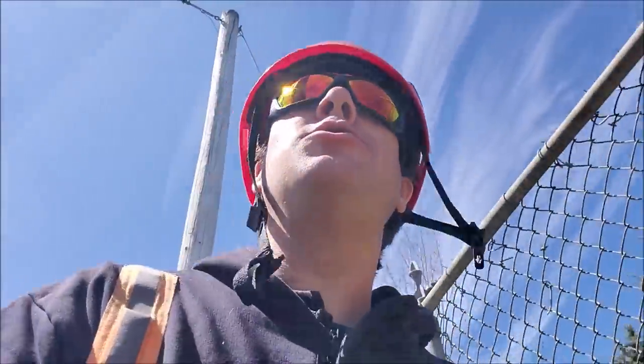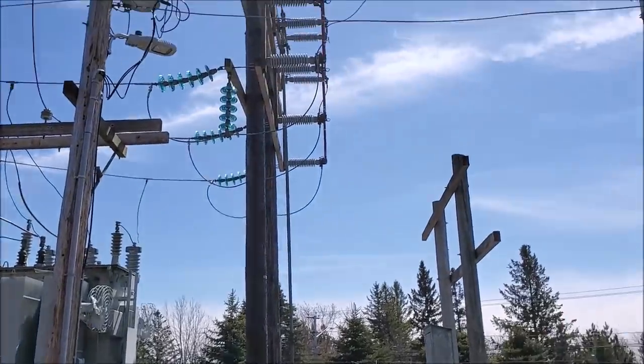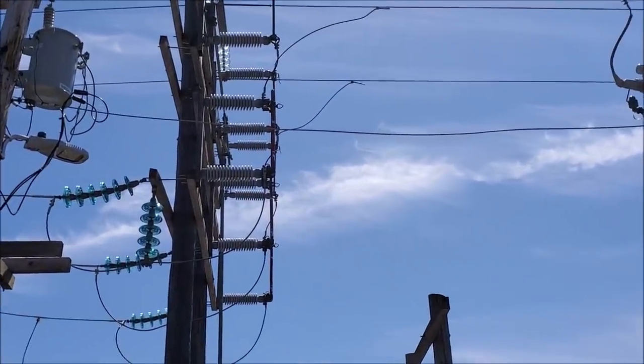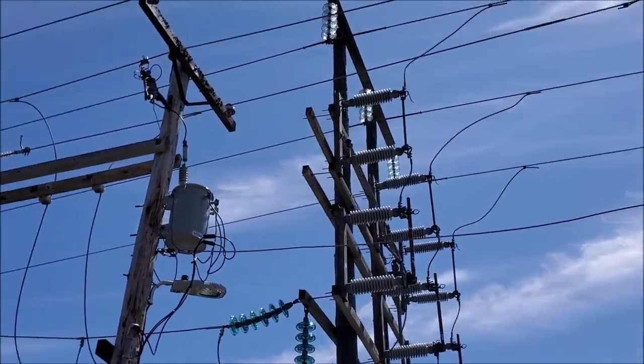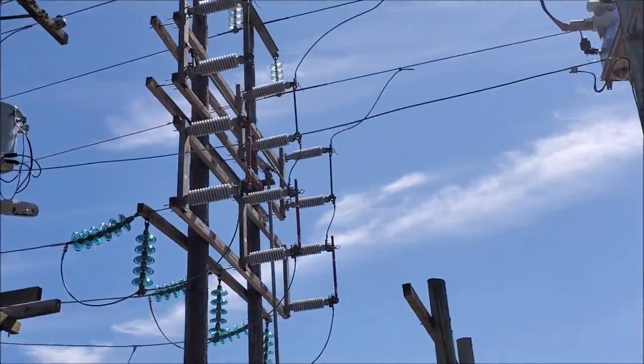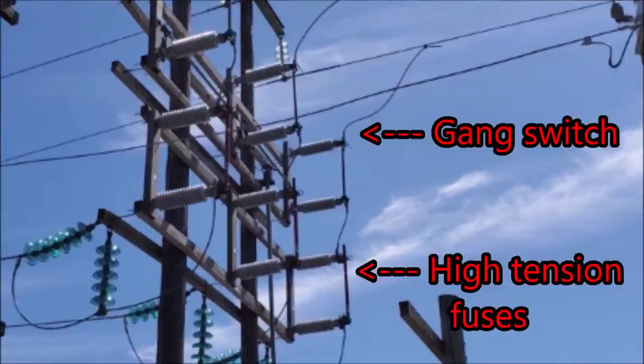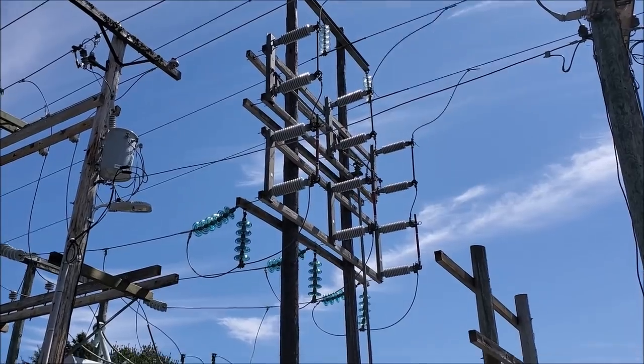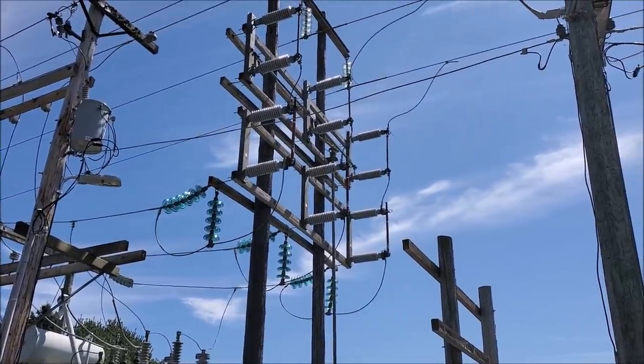So we're going to take a step back to our power transformer again for a second. If there's a fault in the power transformer itself, what we have in that case are these high-tension fuses. You can see there's a set of switches up top, and below that set of switches are those orange fuse barrels. So if there is a fault in this power transformer, those puppies are going to blow. They're violent, they're loud. It's not something that happens very often.